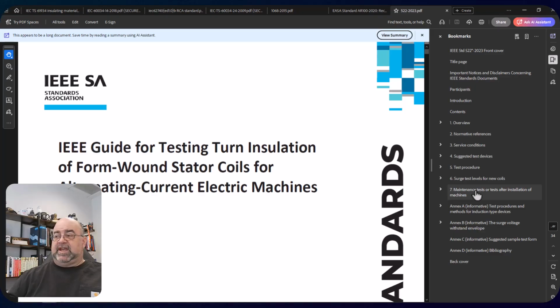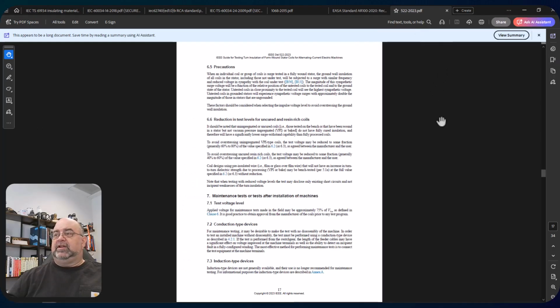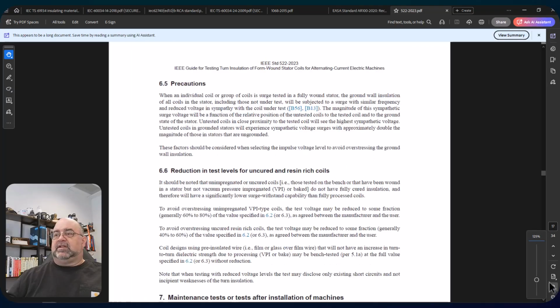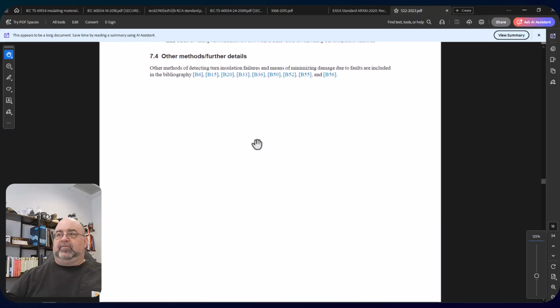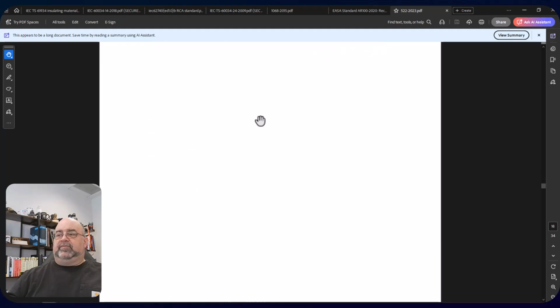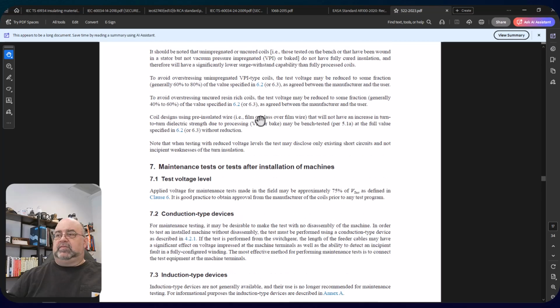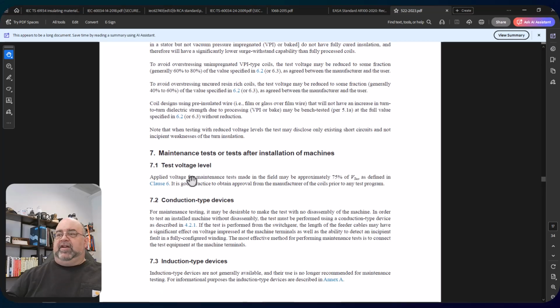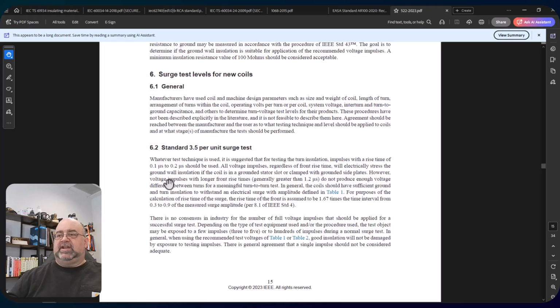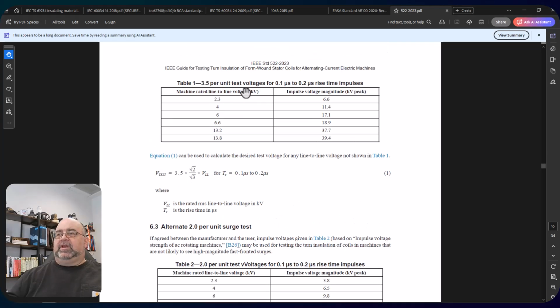Here it is, section 7. This is the one that caused me some confusion as well. Let's go ahead and get this a little bit bigger here. Okay, so the applied voltage for maintenance tests made in the field may be approximately 75% of V test as defined in clause 6. So let's come back here, and this is where they get into it. 3.5 per unit, so that's 3.5 times the voltage rating of the motor. So a 2.3 or 2300 volt machine would be tested at 6600 volts, 4 kV at 11.4, etc.